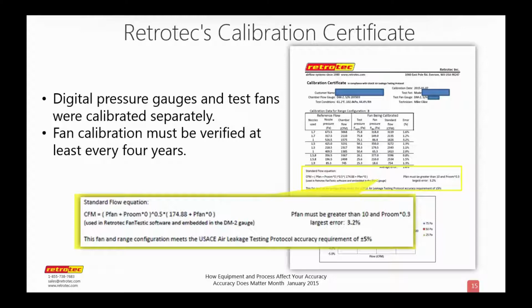It's quite common to have instruments calibrated yearly, and I think it's better to do field calibration checks regularly and have them calibrated if there's a problem. But I just want to make it clear that our calibration requirements are quite long, and usually a local calibration requirement of your particular state could be much shorter. Back to you, John. Thank you.